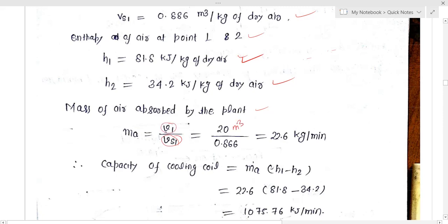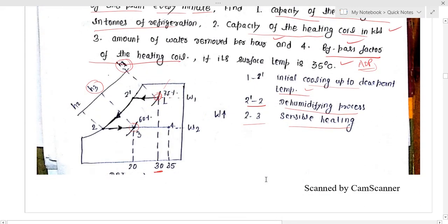Calculate the mass of air circulated per minute: m_a = volume flow / specific volume = 20 / 0.886 = 22.6 kg per minute. The total cooling process covers the entire 1-to-2 process, which includes both initial sensible cooling and dehumidification.